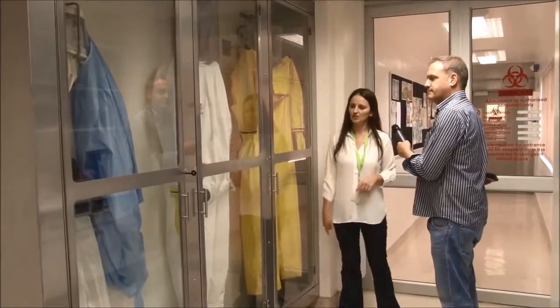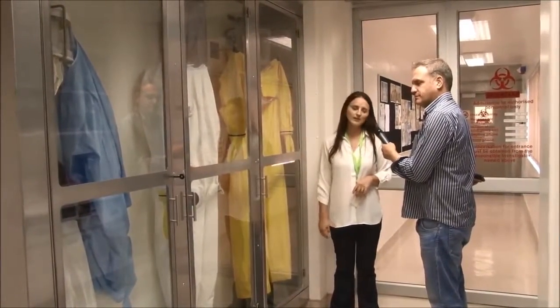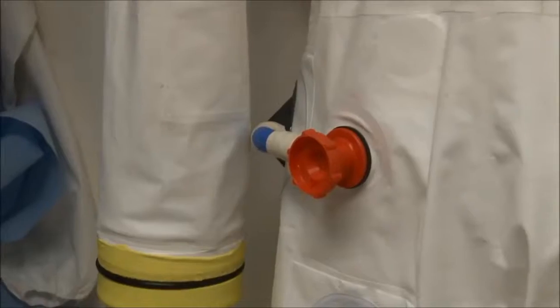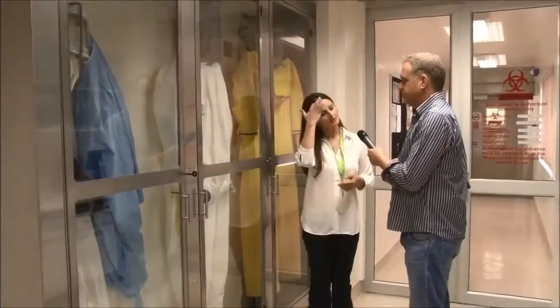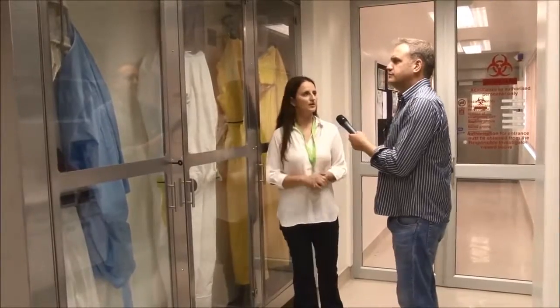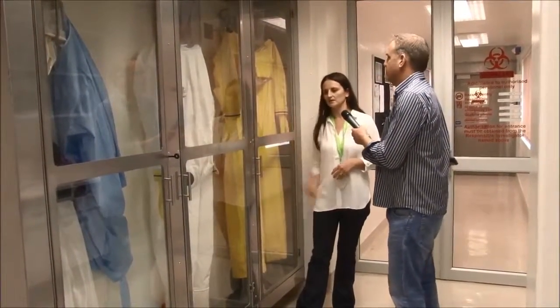Every time, and it gets duly signed. When you have the suit on, you will quickly have to hook up to a breathing air supply. On this suit, it's that tail there that you hook onto breathing air supply coils that are distributed throughout the laboratory — suspended from the ceiling — and you hook in, hook out, and move through the lab. So the suit will puff up with breathing air.